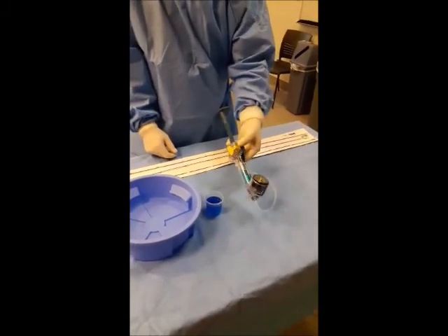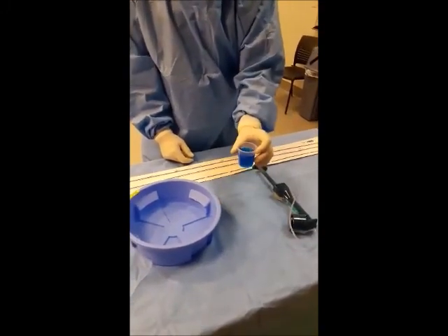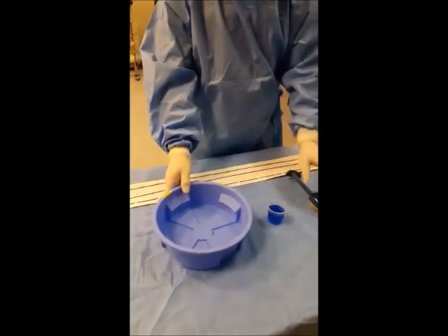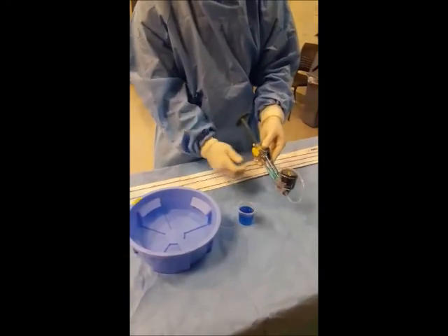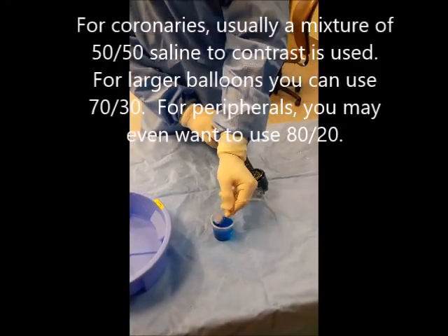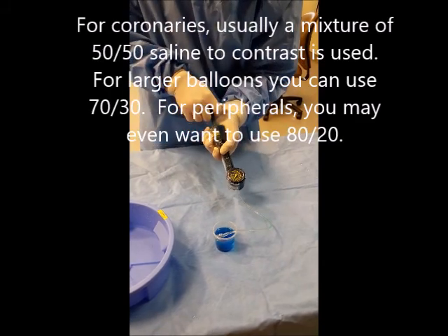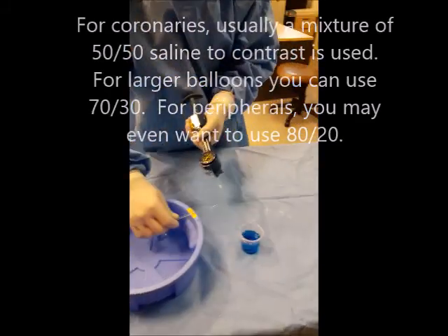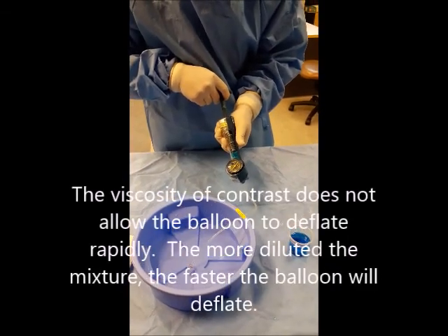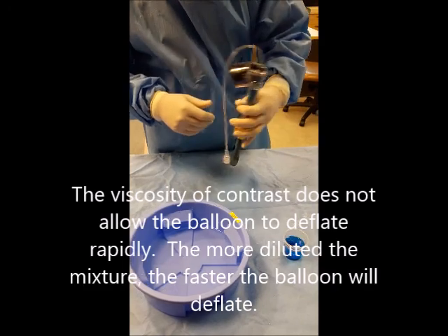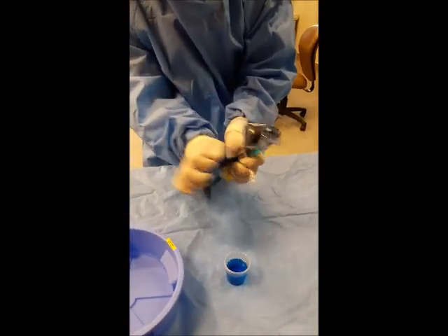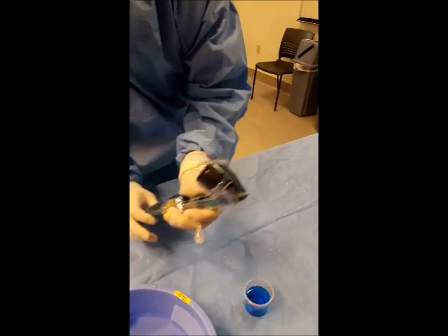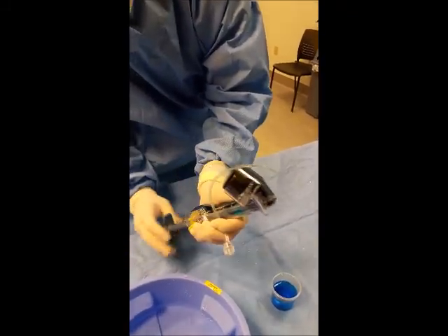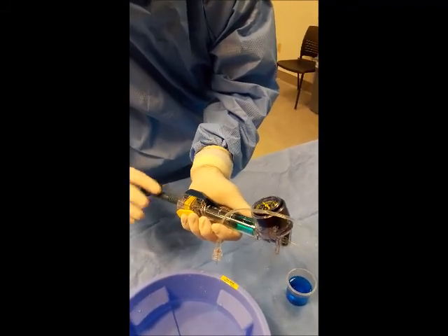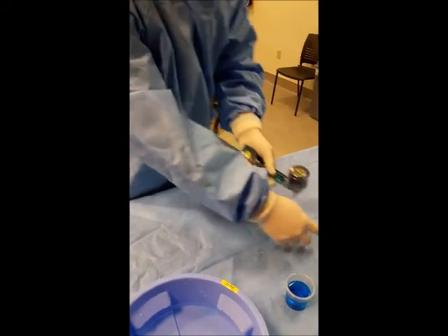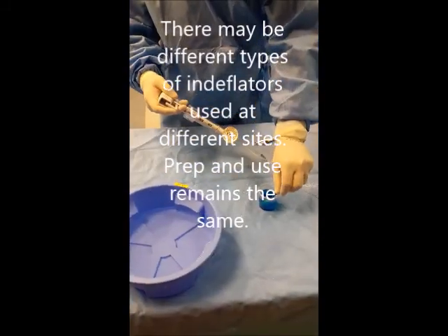Indeflator use, gather your equipment. You will need an indeflator, contrast solution. We usually use Omnipaque, Visipaque, saline. Place the end of the indeflator tubing in the contrast solution and saline and draw negative to obtain your desired ratio mixture. Remove all air out of the indeflator by placing it upside down and either twisting the handle or pushing up the handle to purge the air. You might come across different types of indeflators, but most of the prep is usually the same.